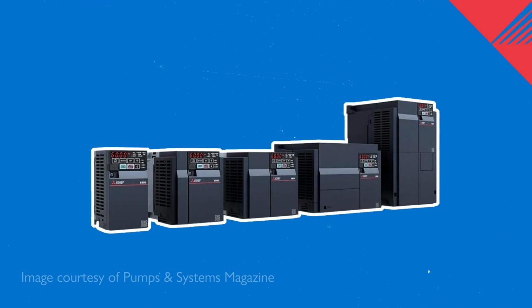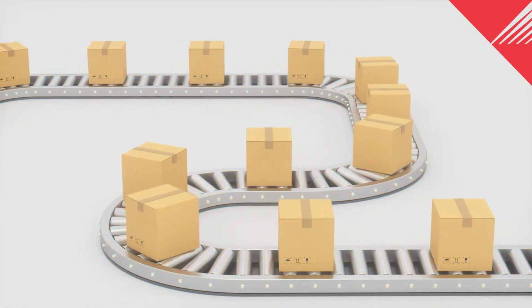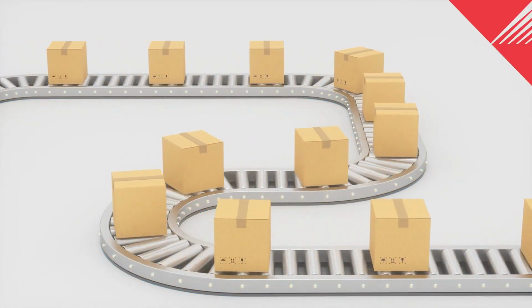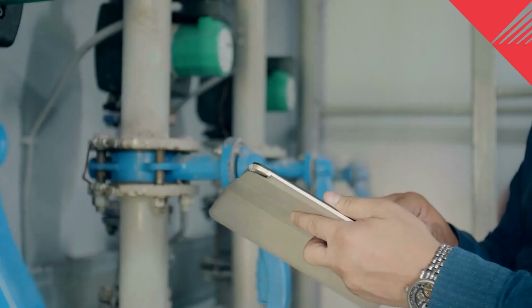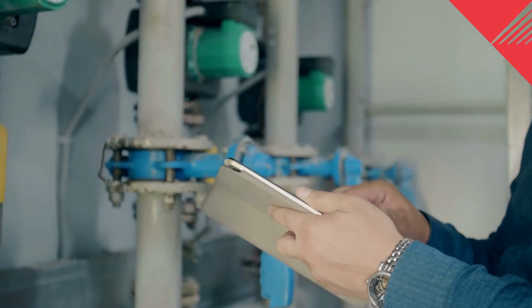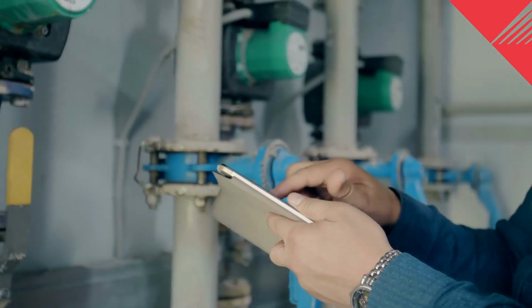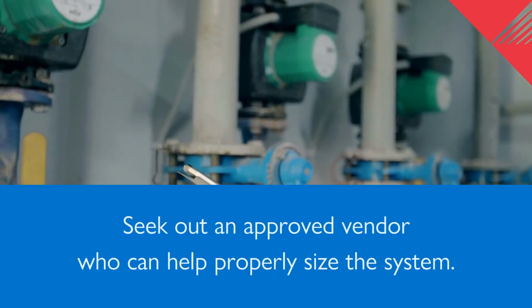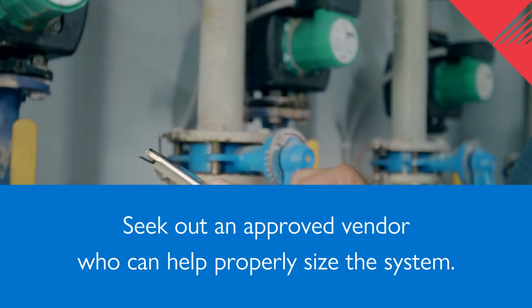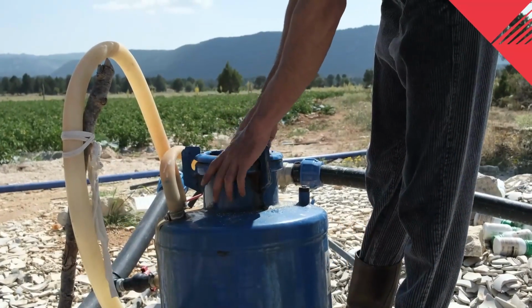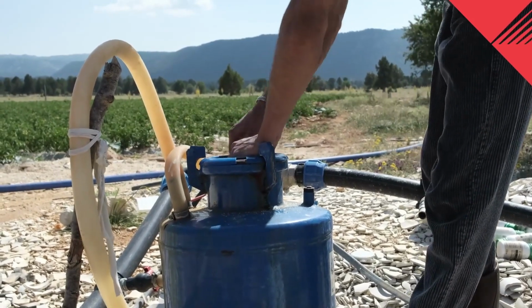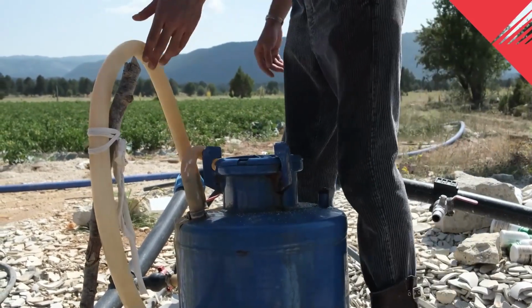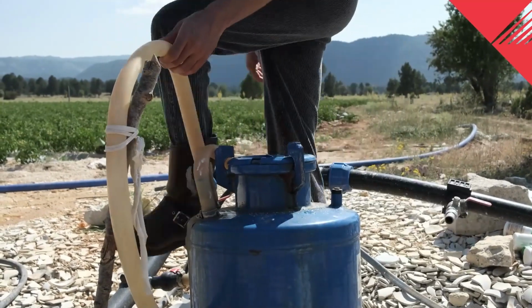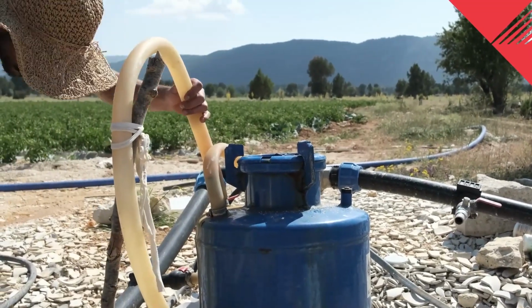Of course, there are times when a motor needs a fixed speed. In certain processes, items like conveyor belts generally require regularity rather than variability. Likewise, if a pump has a dedicated job to do, as long as it's sized properly, a fixed speed is probably suitable. Seek out an approved vendor who can help properly size the system. A VFD may also be a logical choice when certain changes are made to a system. For example, an irrigation pump may have initially had a fixed need, but if the length of the pipe has changed, a VFD could be a money-saving improvement.